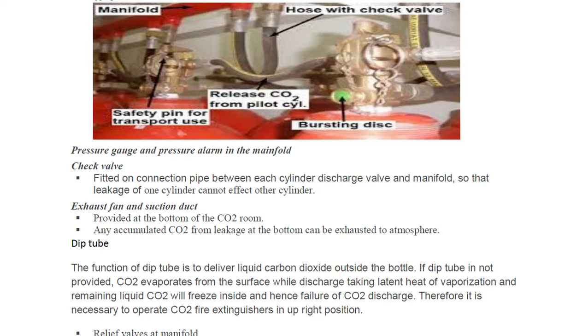In the manifold, we have pressure gauges as well as a pressure alarm — this is self-explanatory. We also have a check valve fitted on the connection pipe between each cylinder discharge valve and the manifold, so that leakage from one cylinder cannot affect other cylinders. That is the reason we have a check valve.